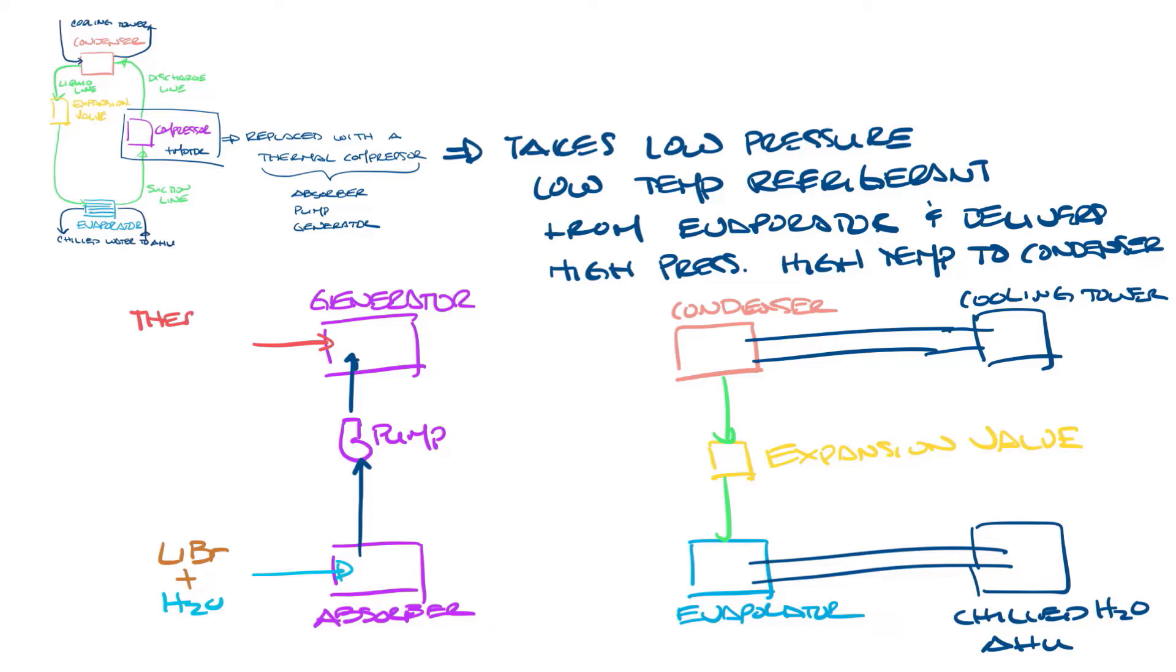In the generator, the refrigerant is boiled using thermal energy. The heat separates the lithium bromide and water. The water vapor leaves the generator and goes to the condenser. The lithium bromide is sent back down to the absorber to start that process over again.